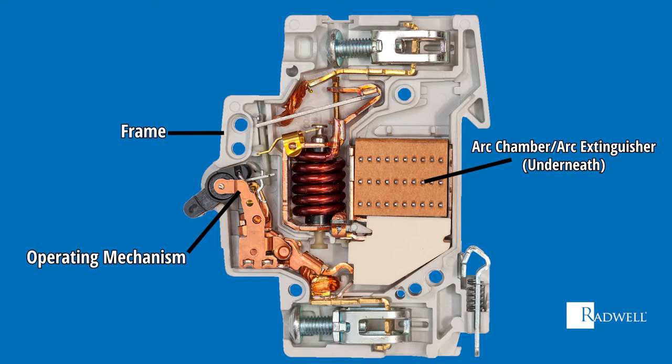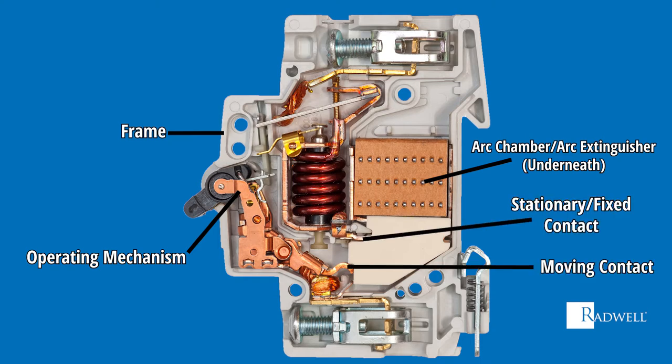The next component is the contacts, which consists of the movable contact, the movable contact arm, the stationary contact, and the stationary conductor. These contacts are what allow the current to flow. Last is the trip unit, which is the most important part of the circuit breaker. The trip unit senses the fluctuation in the current flow and trips the operating mechanism.